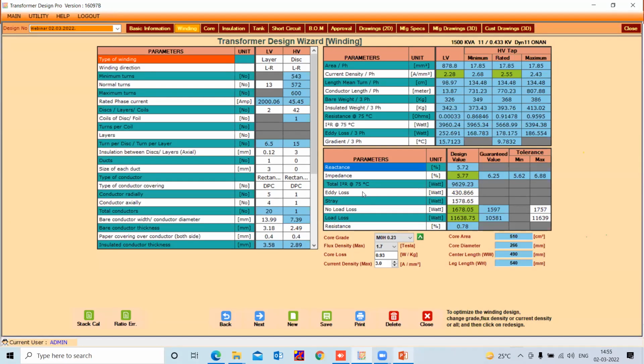Friends, you can see the total I square R loss, the eddy loss. What I see in the white background is all editable by the user. Stray loss is also there, which is again editable. The no load loss is given as designed is 1678. The guaranteed value was 1597 with the tolerance as per the IEC, it takes maximum of 1757.